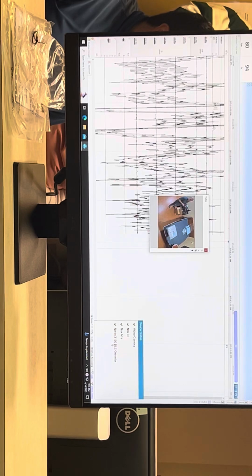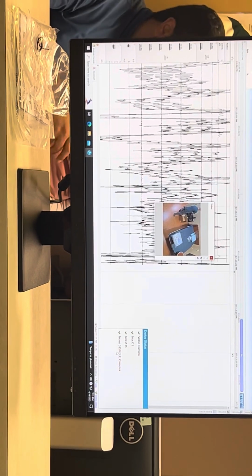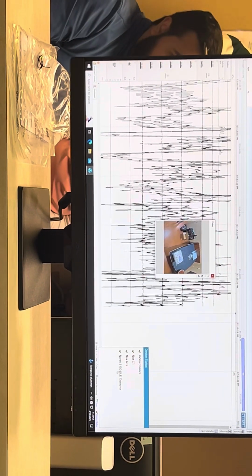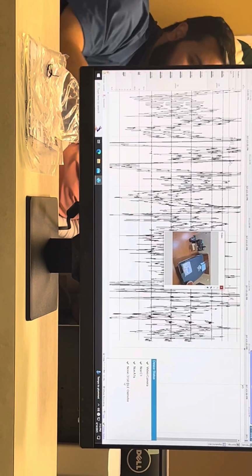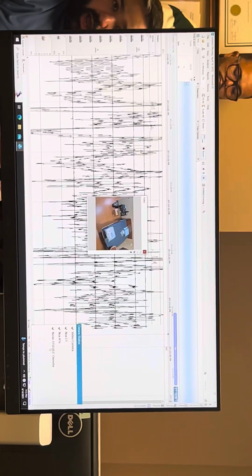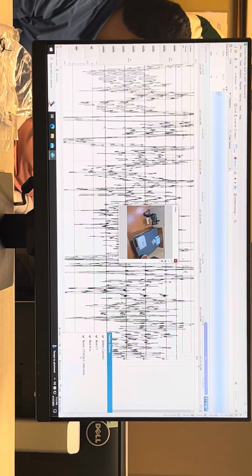The other helpful thing is the running pulse and SpO2 up at the top of the screen here. If you're reading normally throughout the night and all of a sudden these go into dashes, the question then becomes, did your probe come off or did your device die? If you have no numbers here but you still have a check mark down here, that means your batteries are fine, but your patient must have messed with the probe and turned it off. If you lose both, that's most likely your device died. Then you put the batteries back in and connect again.